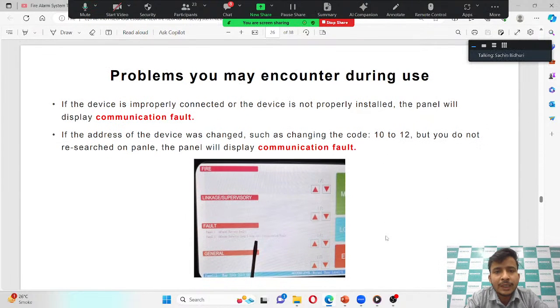So what common fault do you observe during this? It is the communication fault. And what is the reason behind that? If the device is improperly connected or not properly installed, the panel will display communication fault. Whether it is a detector, the MCP or the sounder, if it is not properly installed or the wires are not properly terminated, it will give the communication fault.